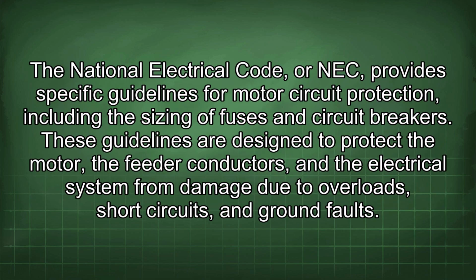The National Electrical Code, or NEC, provides specific guidelines for motor circuit protection, including the sizing of fuses and circuit breakers. These guidelines are designed to protect the motor, the feeder conductors, and the electrical system from damage due to overloads, short circuits, and ground faults.